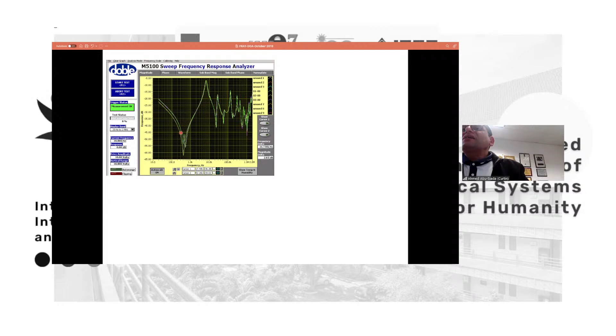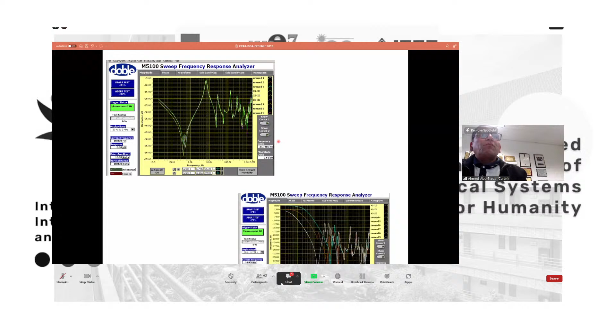If we look at another example, you know now the three phases here are similar to each other. The one to the left here is the middle phase, which is normal. So this transformer is healthy, nothing wrong with it. But if you look at this one, we have significant deviation among the three phases, which reveals a significant problem in at least two phases. So when we took the transformer out of service, I don't think you can observe, can you see that this very strong electromechanical fault happened inside the transformer?